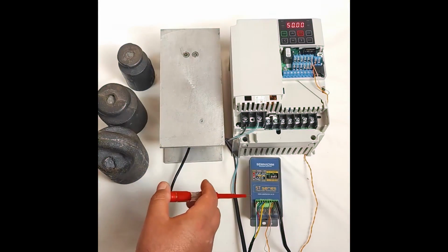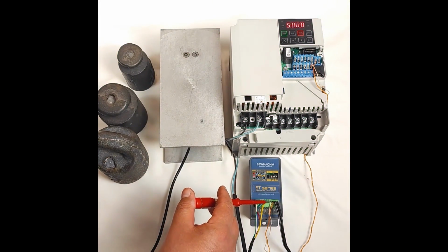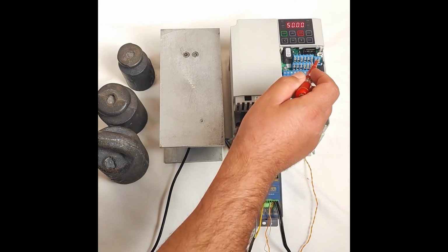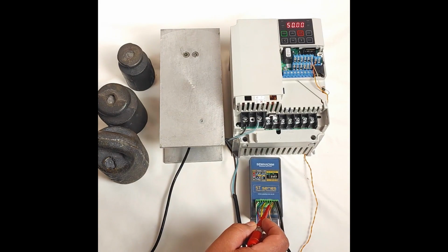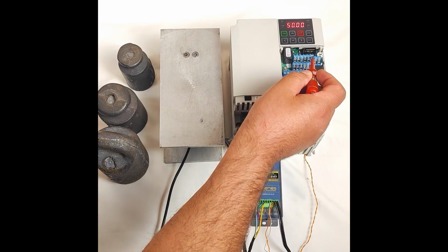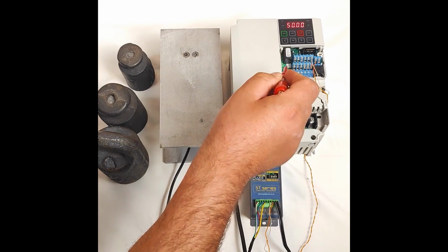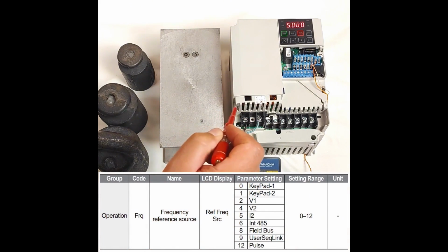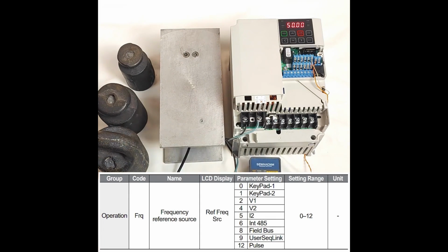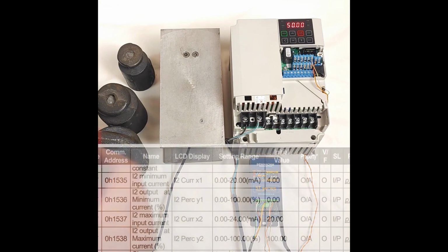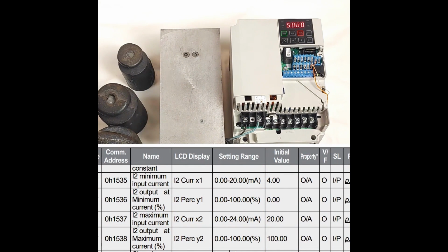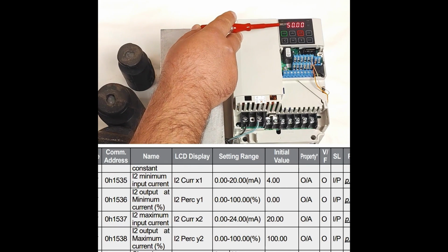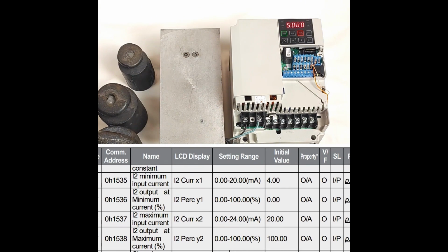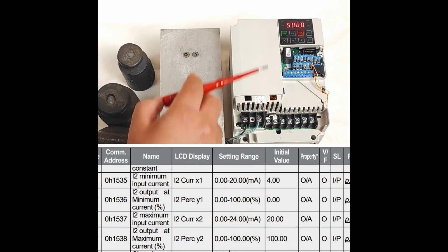Let's test this together. We've calibrated the transmitter, and as you can see, we've connected the transmitter's I to the drive's I2 and the transmitter's GND to the drive's CM. The settings we need to adjust on the drive are shown in the table. We need to change these parameters so that the drive receives the frequency through the analog input. Another important point to consider is that when the transmitter shows 4 milliamps, the drive frequency should be 50 Hz. And when the transmitter output is 20 milliamps, the drive frequency should be 0.